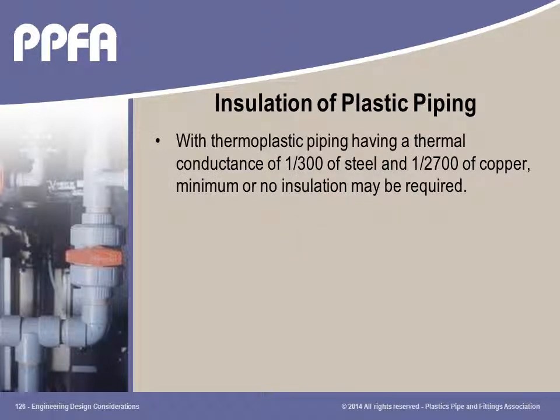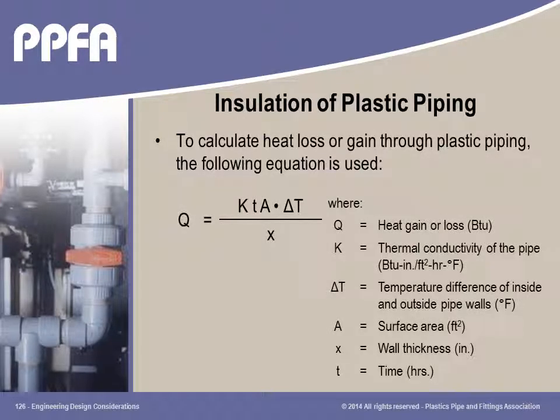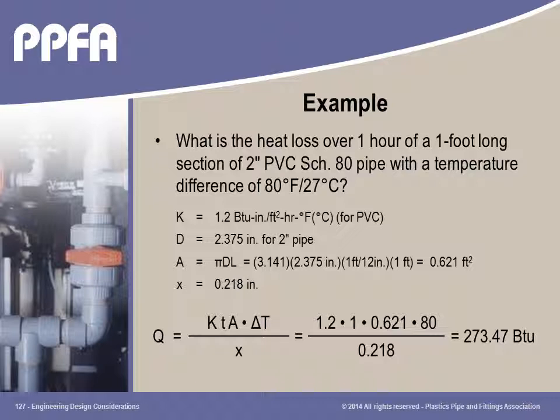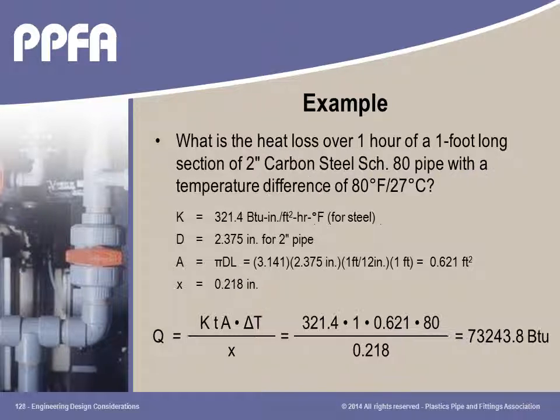Heat loss in metal piping is about 200 to 300 times greater than that of plastic. Therefore, plastic piping requires less insulation than metal piping systems. To calculate the heat losses of any piping material, use the listed equation. In the example, PVC had a heat loss of 273.5 BTUs. With similar conditions of service and pipe diameter using steel pipe, the heat loss of 73,243.8 Btu is almost 268 times as much as PVC.